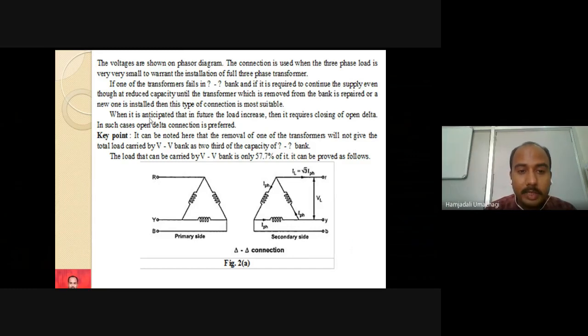When it is anticipated that the load will increase in future, then closing of the open delta is required. In such cases open delta connection is preferred. If the load is small, we can make use of open delta, but if the load increases, you should increase the rating of the transformer. So in that case we should close the open VV connection. Once we close it, its kVA rating increases, and that kVA rating can support the increased loading conditions. Then it becomes a delta connection, which can support a large load. That is the meaning.